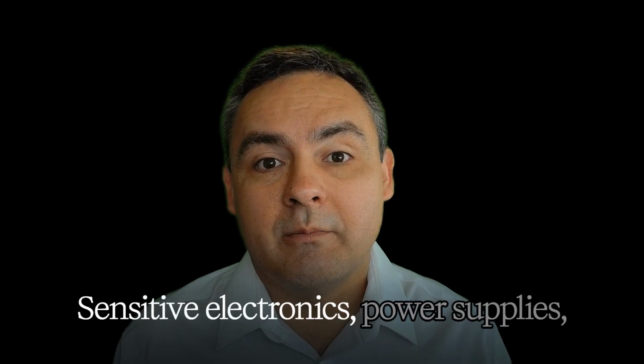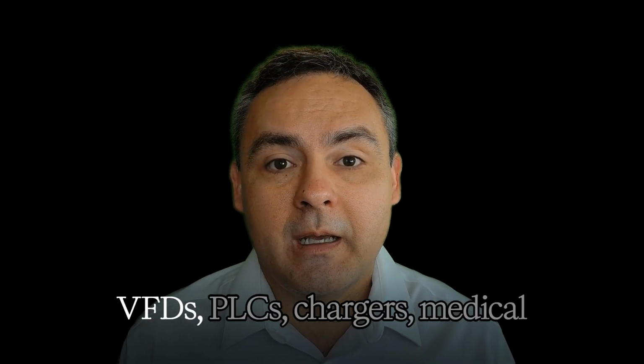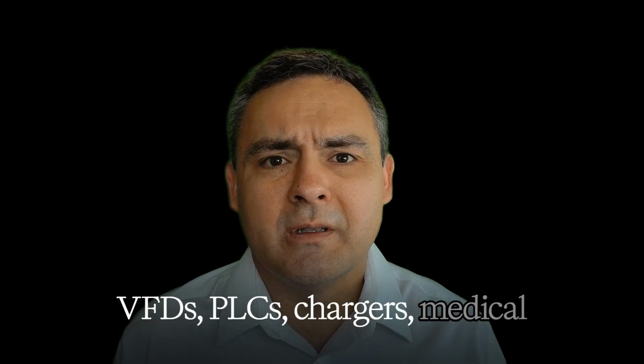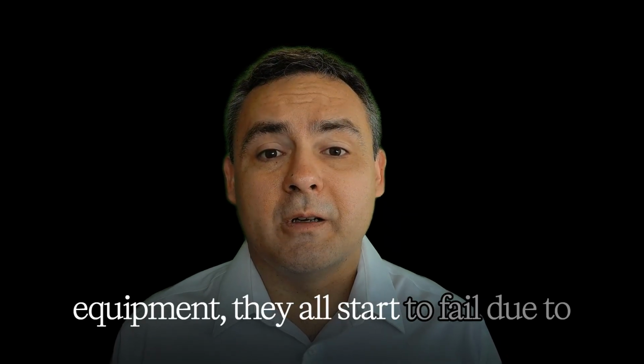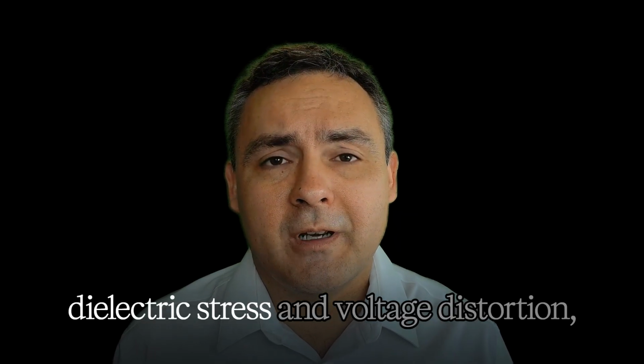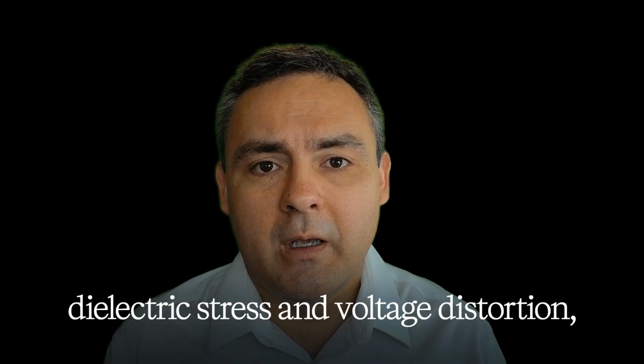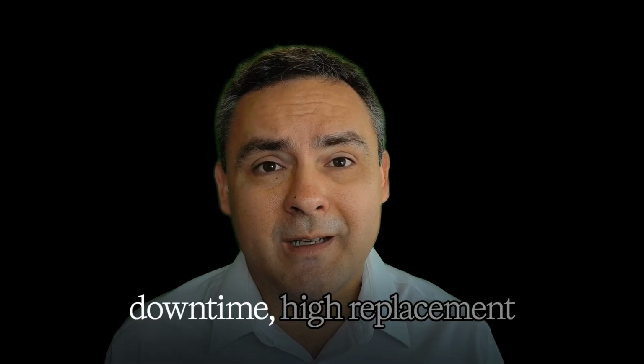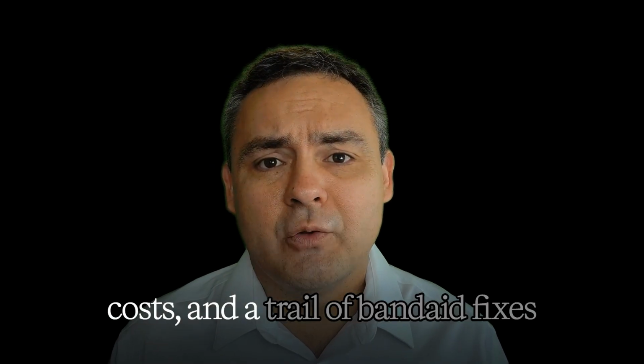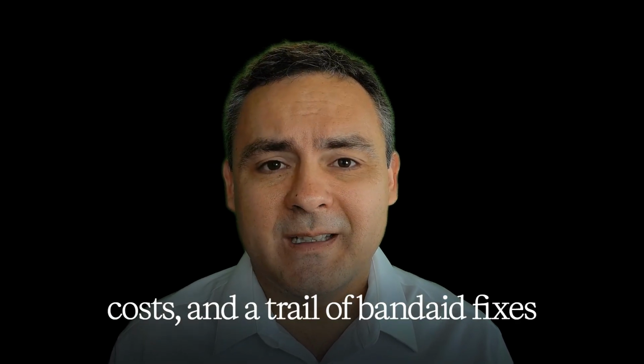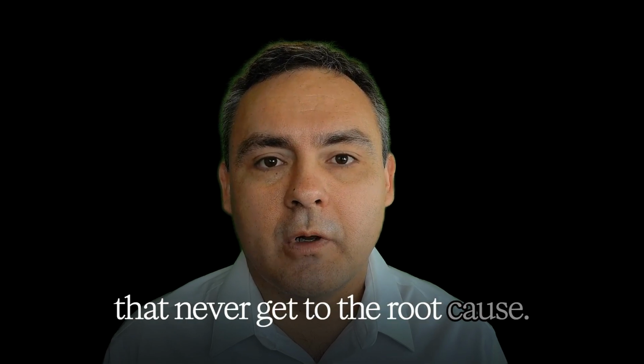Sensitive electronics, power supplies, VFDs, PLCs, chargers, medical equipment, they all start to fail due to dielectric stress and voltage distortion. We may end up with mystery downtime, high replacement costs, and a trail of Band-Aid fixes that never get to the root cause. Most utilities don't fine us yet for IEEE 519 non-compliance, but it's coming.